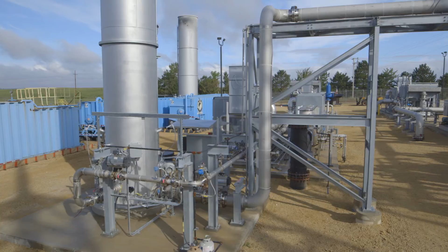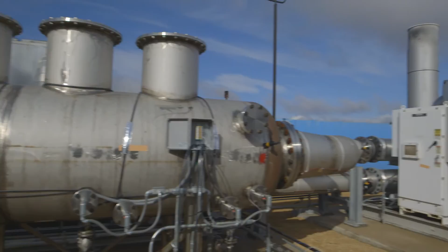In addition to removing the H2S, we have to further prepare the fuel here, so that also means we're going to be removing water. Our first stage of removing that water is this vessel here. The water comes in, we remove the heavier water, it drops out and goes back to the landfill's leachate system. These blowers at that point are pulling the gas forward. It'll take it on to your first initial cooler. This is an ambient air cooler. You'll come back across, you have another set of blowers, which will bring you to another ambient cooler. Then you come to the chiller section.